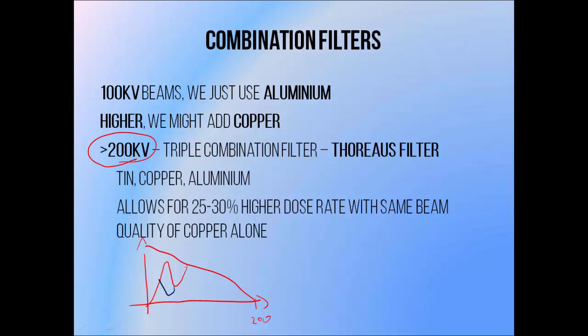This has the effect of contributing to the portion directly below the bit you're cutting out. So you add another layer to your filter, which cuts out this portion that was added and contributes some more that's a slightly lower energy. So you add another layer which cuts this out too, until the energy that's emitted by the filter layer is negligible. Bear in mind that this whole time you're also attenuating the higher energy beam components too, just to a lesser degree than the lower energy.